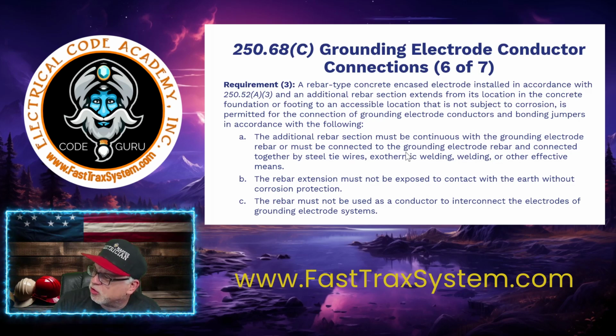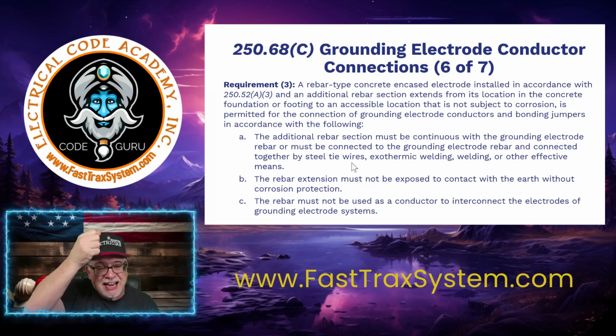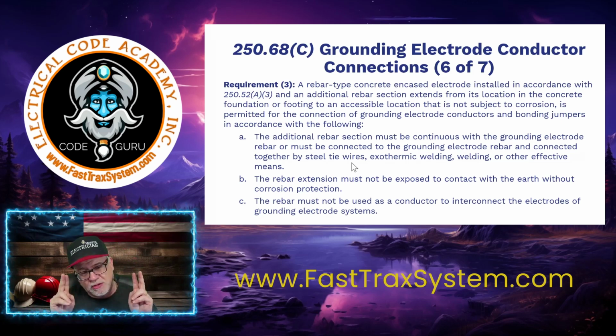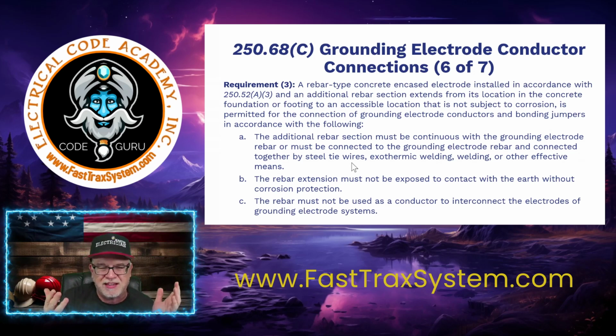It must be connected to the grounding electrode rebar and connected together by steel tie wires, exothermic welding, or other effective means. So the rebar that comes up has to extend down to the concrete encased electrode that is down in the 2-inch encasement. It has to then be connected to it with tie wires, exothermic welding, normal welding, or any other effective means. Check with your AHJ to see what they find acceptable. Typically, steel tie wires is what people tend to use, because that's usually what they use to interconnect the rebar configuration or the grid.